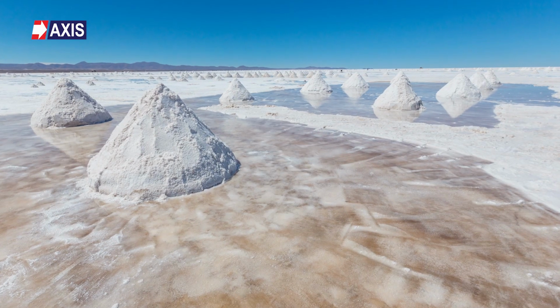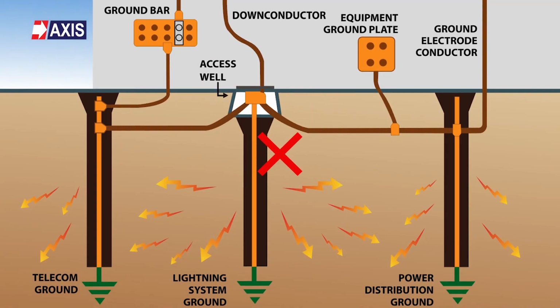Conventional earthing systems degrade over time because they use layers of salt and charcoal, while the salt leaches out and corrodes the earth electrodes used in the system. Salt and charcoal are also less conductive materials and are not able to effectively dissipate fault currents the way other, more specialized earthing materials can. As a result, it is not an effective or reliable method for providing earthing.